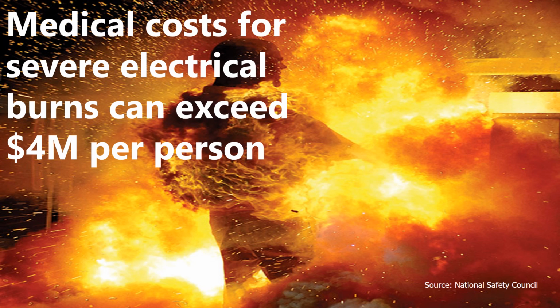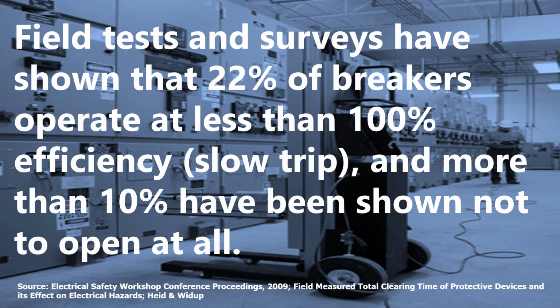Medical costs for severe electrical burns can exceed $4 million per person. Now, the cost of their treatment and rehabilitation is huge. Another significant statistic is that field tests and surveys have shown that 22% of breakers operate at less than 100% efficiency, i.e. there's a slow trip, and more than 10% have been shown not to open at all. So we rely on our breakers, and this is why breaker maintenance is so important, because if the breakers don't operate, then our calculated arc flash exposure is much higher than what we've calculated it to be.